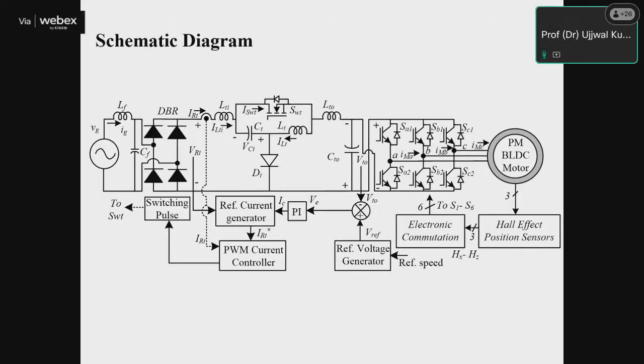The output of the DSP controller is fed to the IGBT switches through optocoupler switches - we use optical isolation between the power switches and the controller side. So if any fault occurs at the power converter side in the switches, it should not be transferred to the controller side. That's all about this scheme.